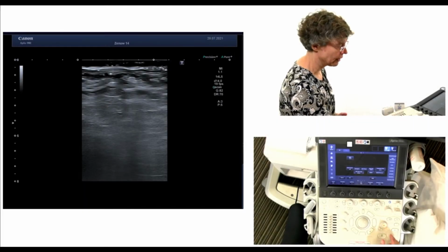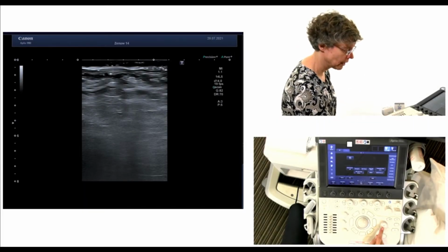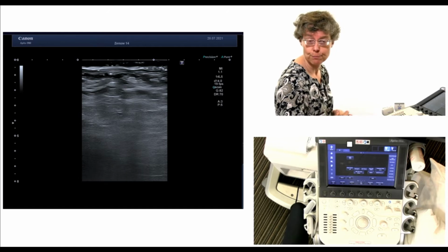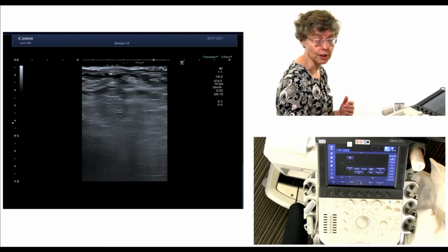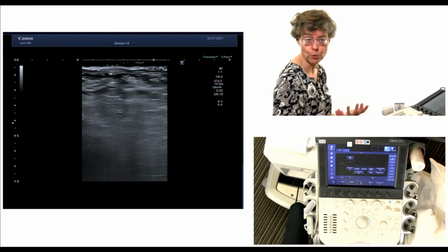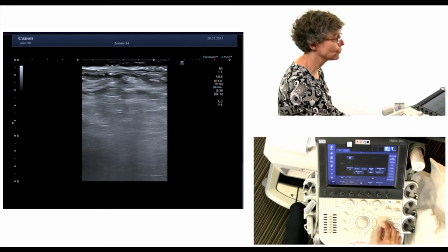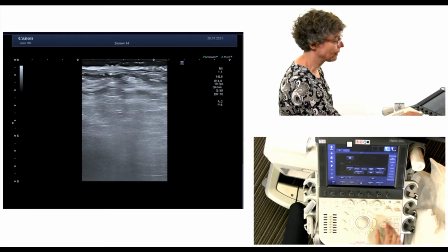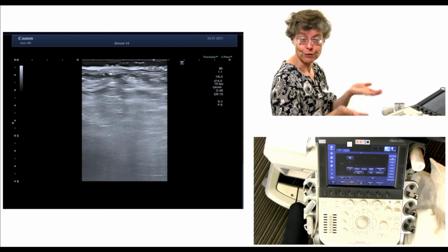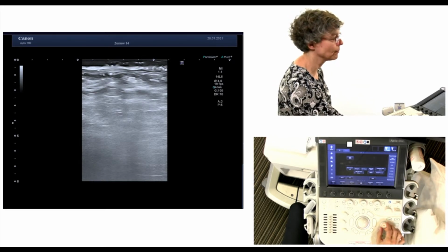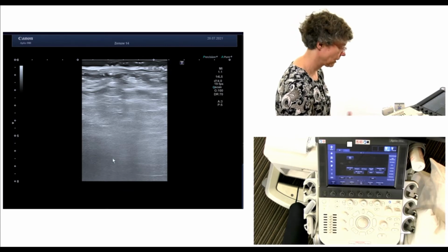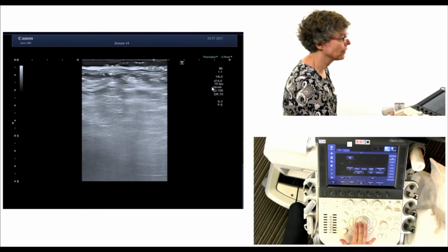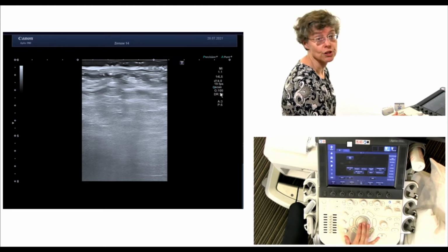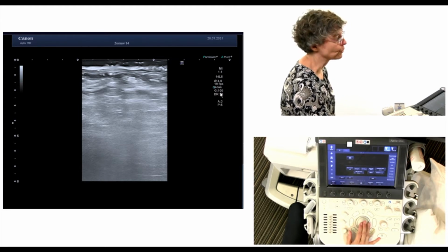But let's just say that you want to have a clearer image. Here's a button called 2D, and it's basically the volume knob on this machine. It's ultrasound, which means it's sound waves in decibels, and you're just turning up the volume by turning this knob. So everything that gets back to the transducer is sort of enhanced, and you can see the whole screen becoming brighter as I adjust the gain. Maybe you didn't see it the first time, but there is a little indicator here that says G, which is gain, and it says 100 right now.